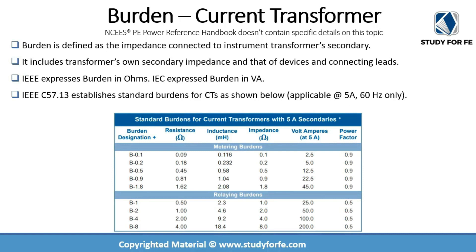IEEE standard C57.13 establishes standard burden ratings for CTs, which are shown in this table. An important point to remember is that these ratings are applicable for 5 amps and 60 hertz systems only. So these are standard CT burden ratings with 5-amp secondaries.